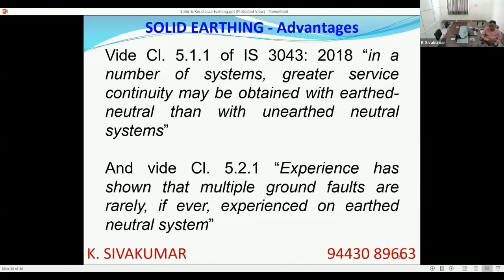Similarly, we have also seen that in the ungrounded system there are chances of restriking faults, because once one phase gets grounded, the voltage of the other two healthy phases with respect to earth shoots up by 1.732 times, root 3 times. So there is a voltage stress, and there are always chances of arcing faults, repeated or multiple ground faults. As I told you, the second phase insulation with the ground is stressed, and sooner or later a second fault appears, maybe a third fault. In an earthed neutral system that is not possible, because even when one phase is grounded, the ground potential appears in that phase rather than phase potential appearing in the other two phases. The other two phases are always kept at neutral potential, so they are not stressed. Also, the earth fault current is very significant, so there can be the quickest possible isolation, so that the healthy system is not stressed. This is also documented in IS 3043 as an advantage of the solidly earthed system.